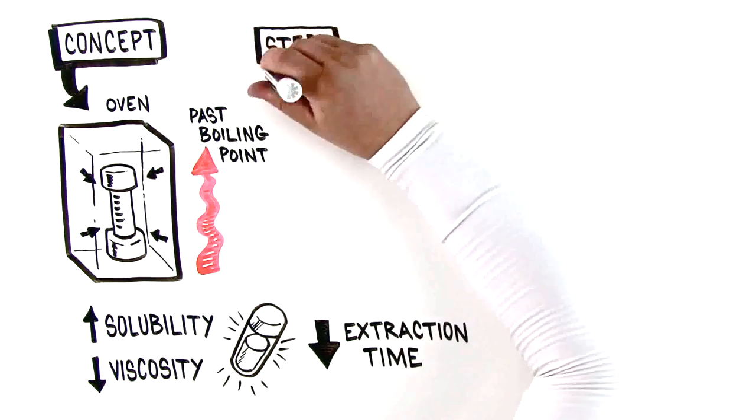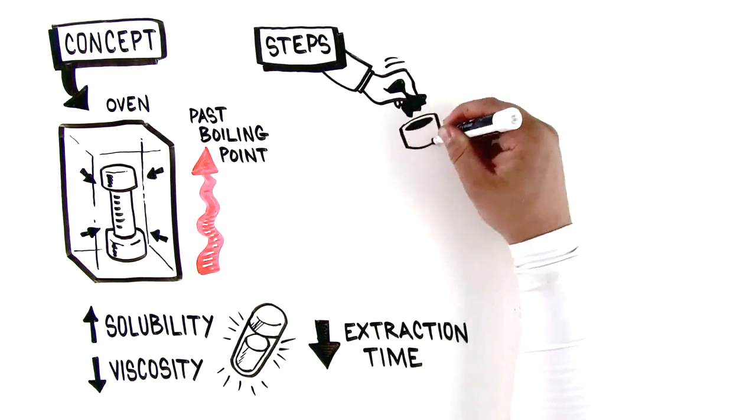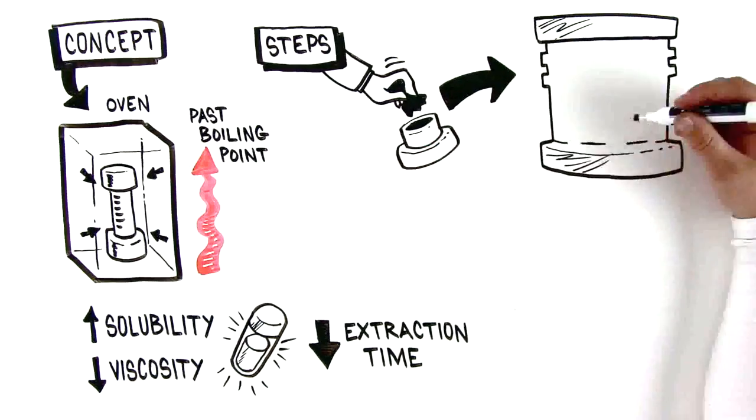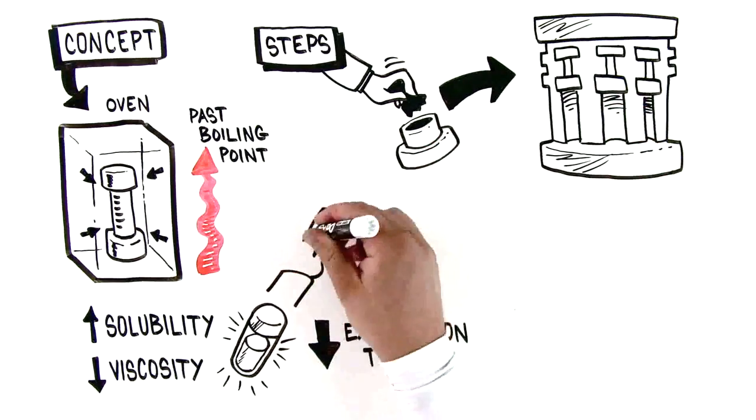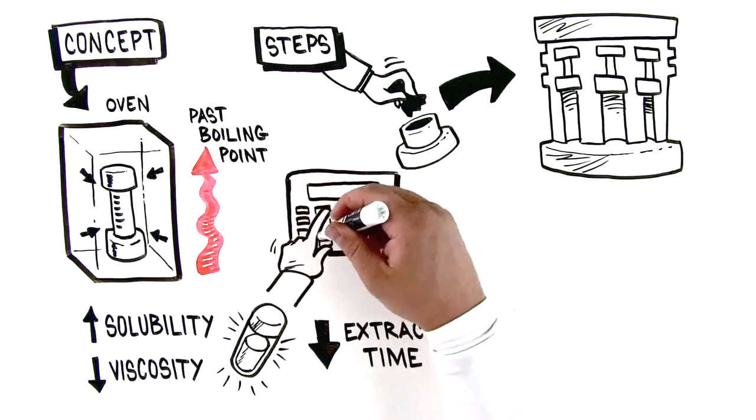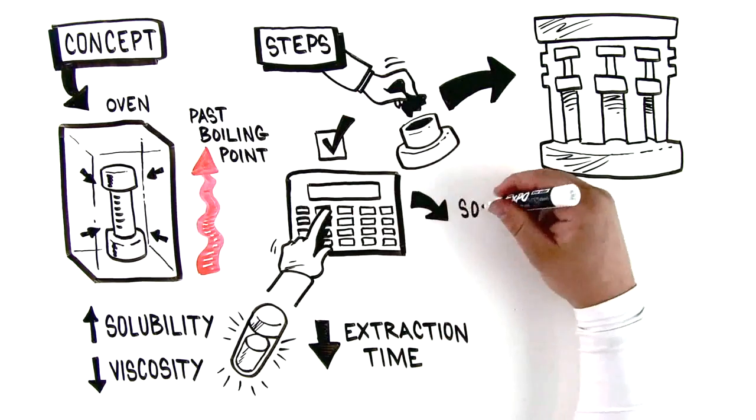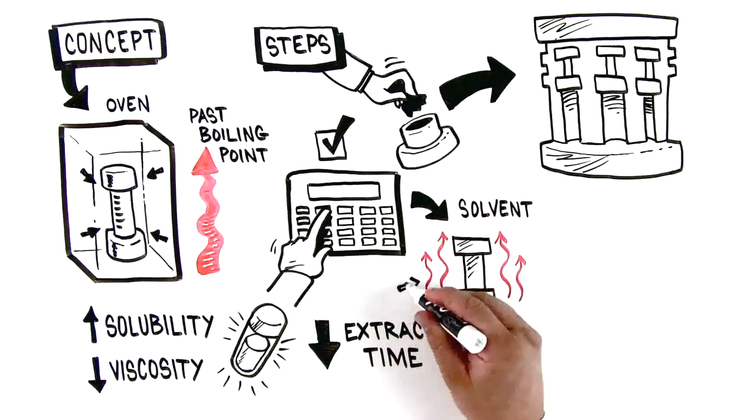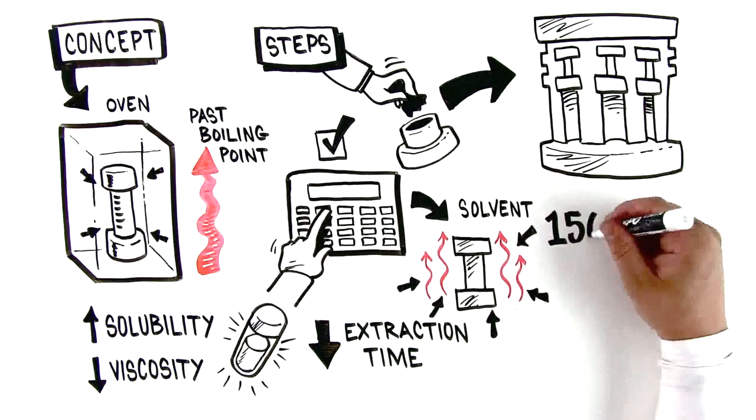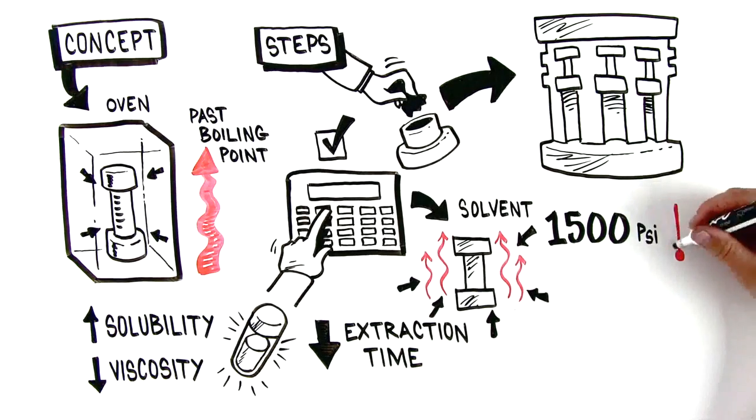Here are the steps. Add the prepared sample to the extraction cell and place the cell into the carousel. Select a pre-programmed extraction method and the system will automatically begin the extraction. The system fills the cell with solvent, heats, and pressurizes, keeping a steady 1,500 psi and desired temperature.